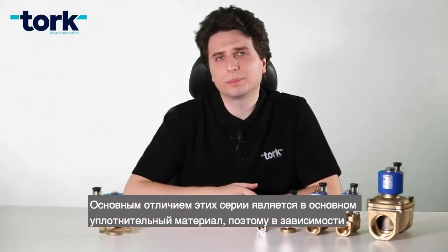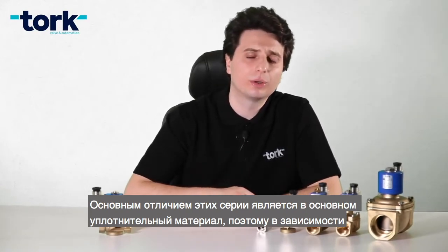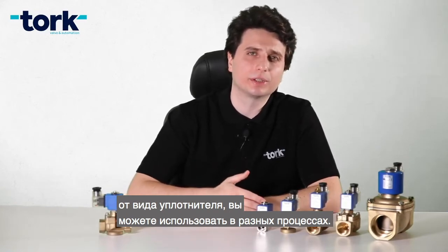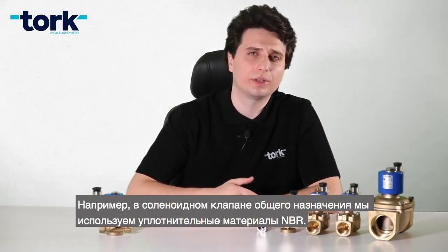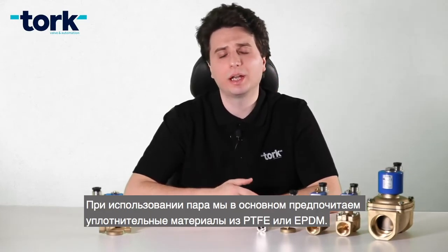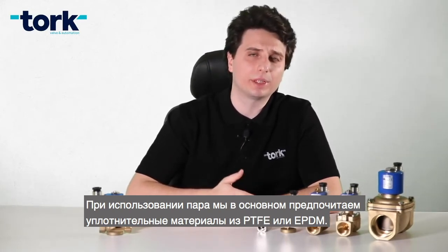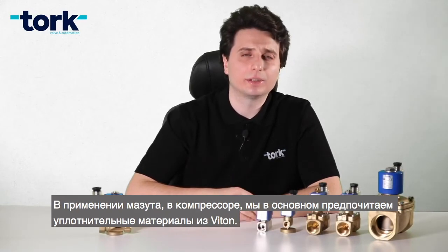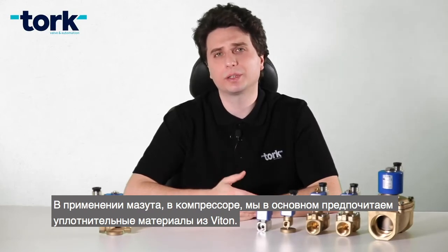The main difference among these series is mainly the sealing material. With different kinds of sealing material, you can use them in different kinds of applications. For instance, in general purpose valves, we are using NBR sealing materials. In steam application, we mainly prefer PTFE or EPDM sealing materials. And in fuel oil application and compressor application, we mainly prefer Viton sealing materials. So, mainly the sealing materials differ between these series.